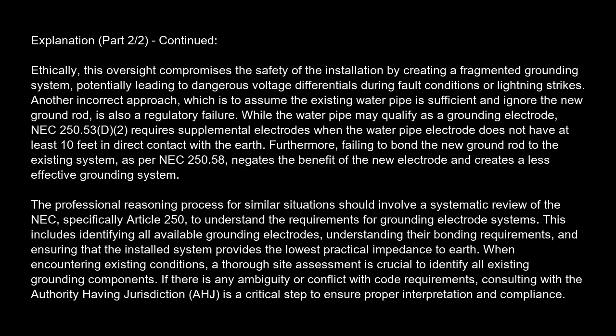The professional reasoning process for similar situations should involve a systematic review of the NEC, specifically Article 250, to understand the requirements for grounding electrode systems. This includes identifying all available grounding electrodes, understanding their bonding requirements, and ensuring that the installed system provides the lowest practical impedance to earth. When encountering existing conditions, a thorough site assessment is crucial to identify all existing grounding components. If there is any ambiguity or conflict with code requirements, consulting with the authority having jurisdiction (AHJ) is a critical step to ensure proper interpretation and compliance.